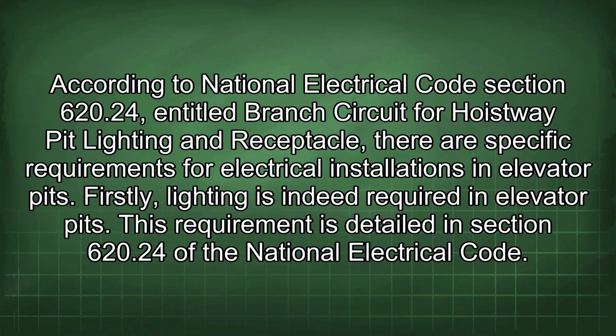According to National Electrical Code Section 620.24, entitled Branch Circuit for Hoistway Pit Lighting and Receptacle, there are specific requirements for electrical installations in elevator pits. Firstly, lighting is indeed required in elevator pits. This requirement is detailed in Section 620.24 of the National Electrical Code.